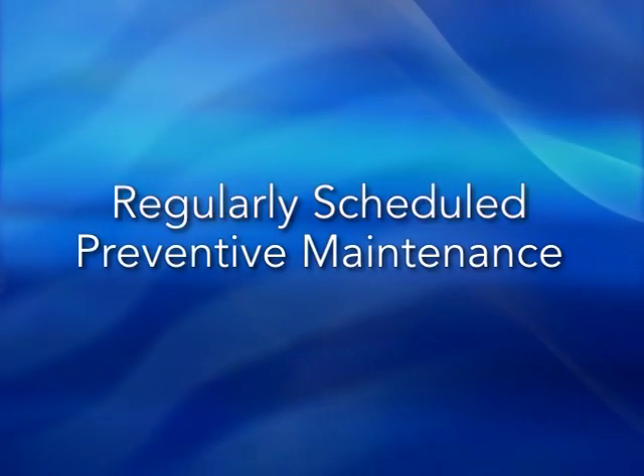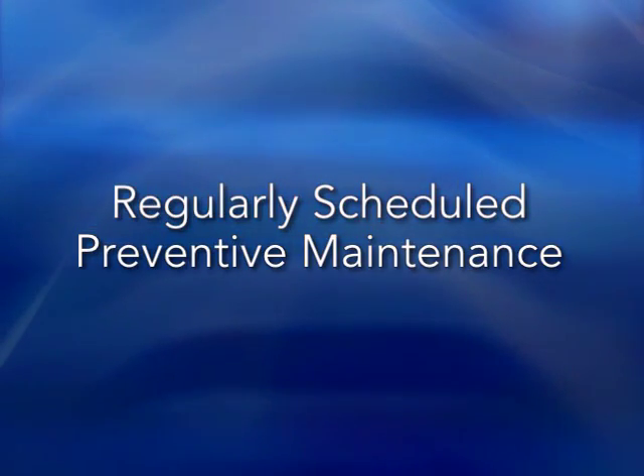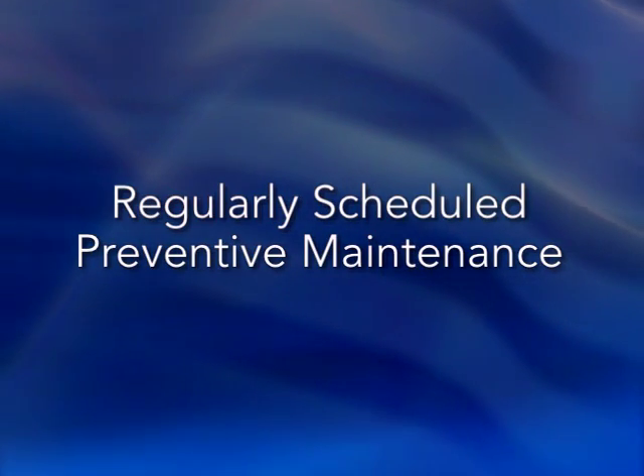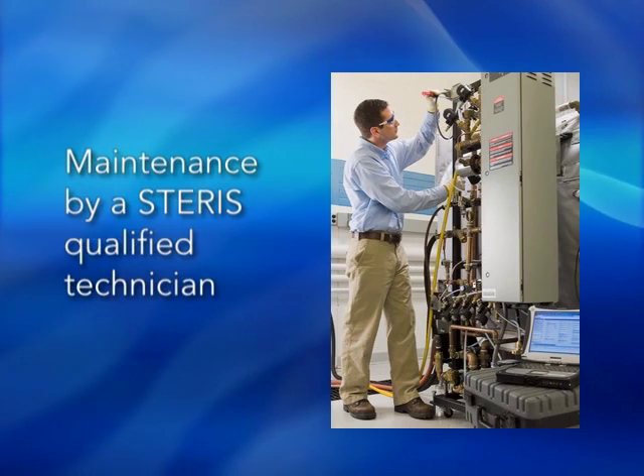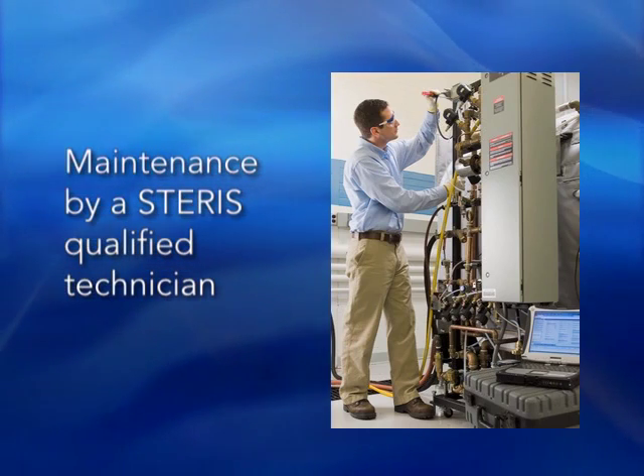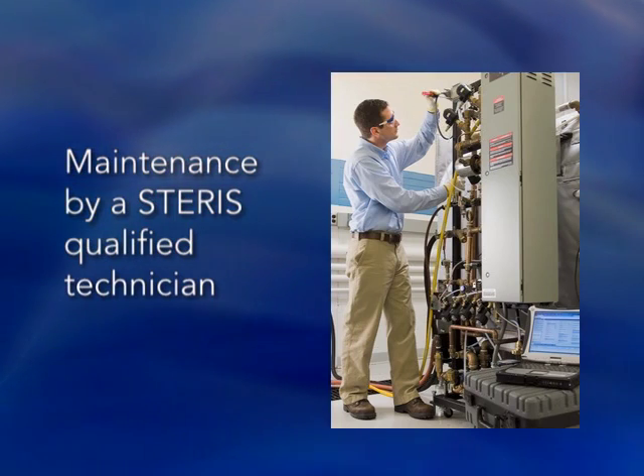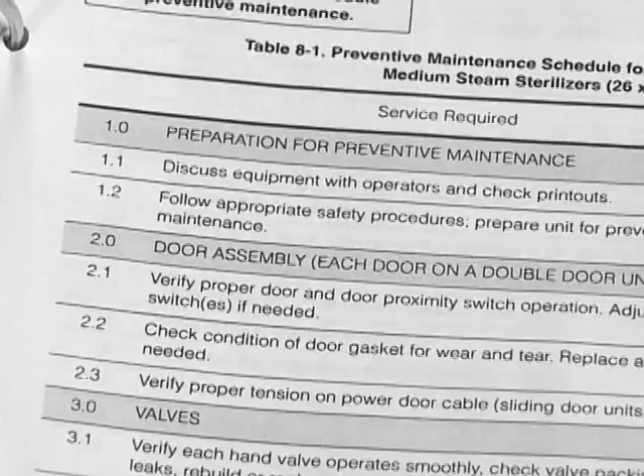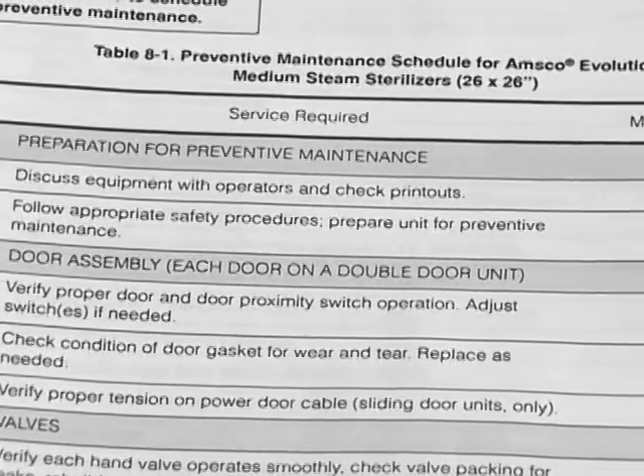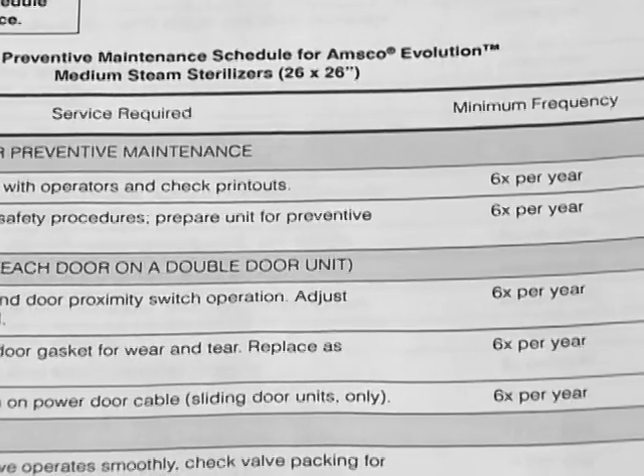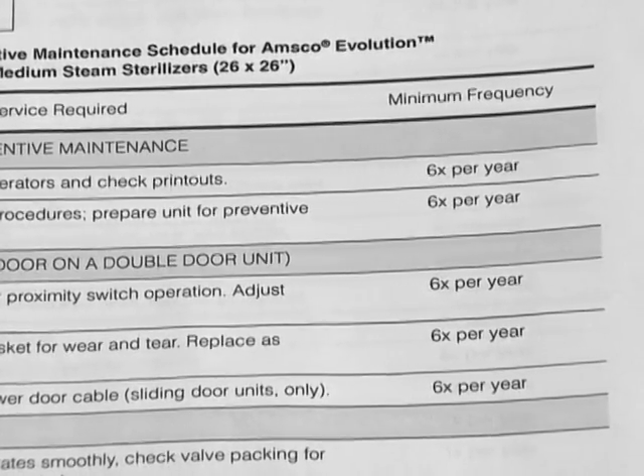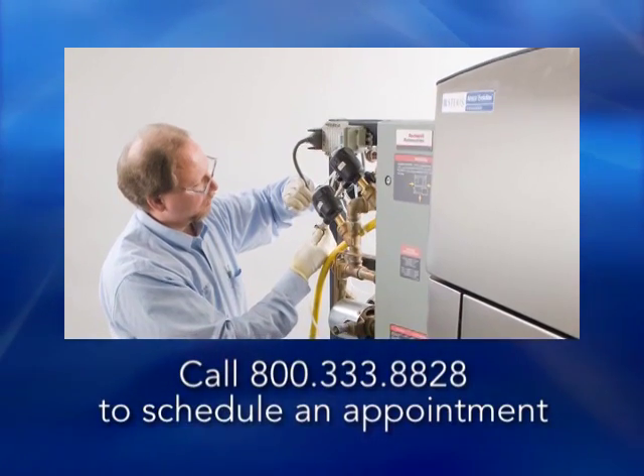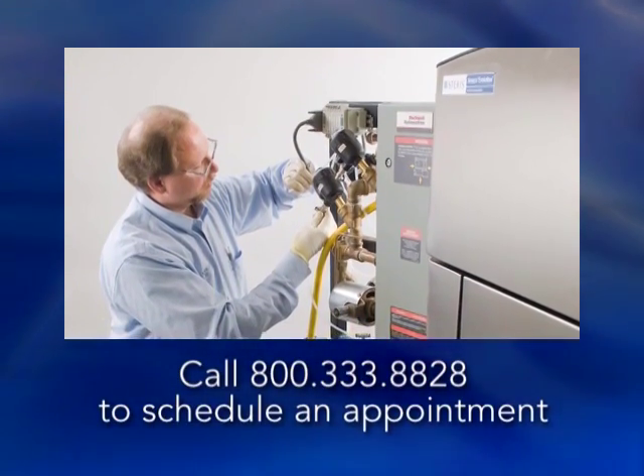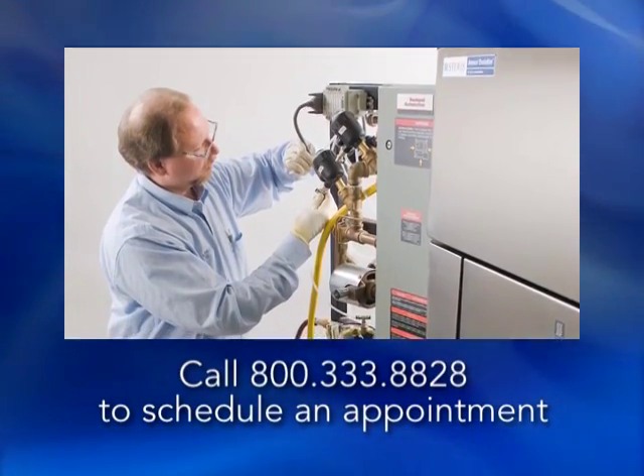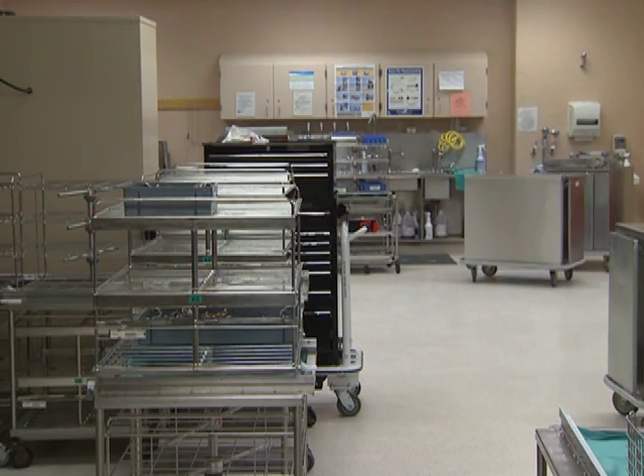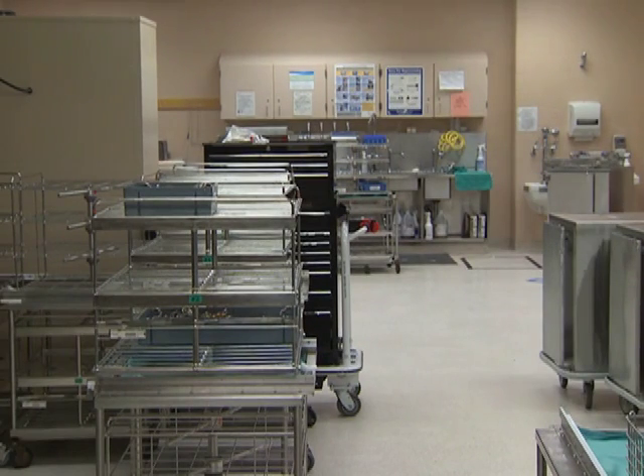In addition to routine maintenance, regularly scheduled preventive maintenance is essential for ensuring peak performance and avoiding unscheduled downtime. Certain preventative maintenance activities must be done by a STERIS service technician or a STERIS-trained service technician in your facility. Refer to Table 8-1 in the Routine Maintenance section of the Evolution Sterilizer Operator Manual for a complete list of maintenance activities. To schedule a maintenance appointment with a STERIS service technician, call 800-333-8828.